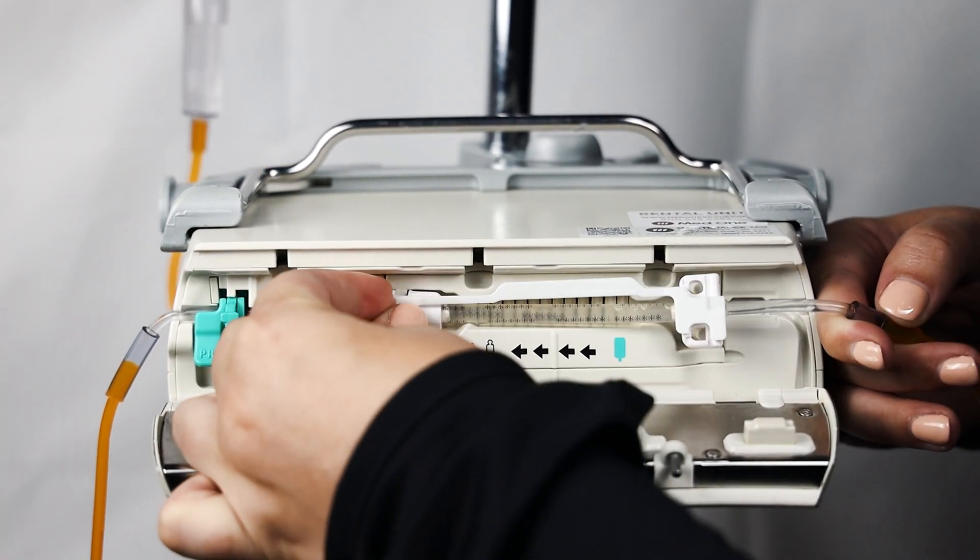Clinicians can use dedicated B. Braun tubing sets when operating this IV pump. This pump features a flow rate range of 0.1 to 1200 milliliters per hour.